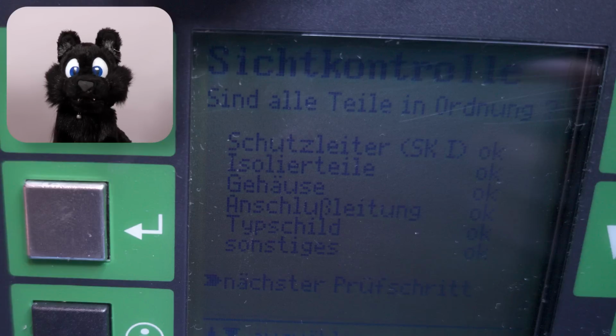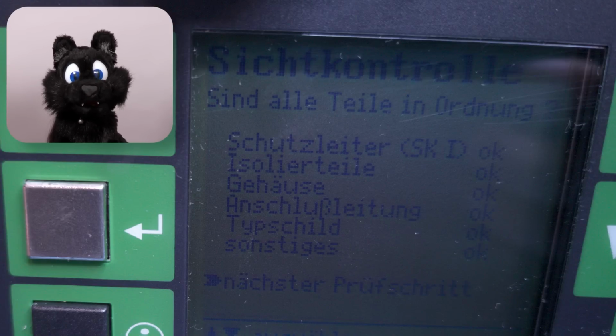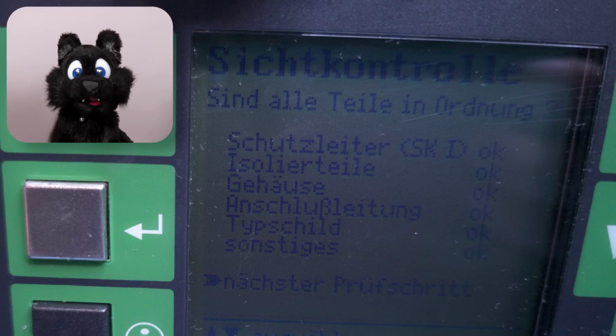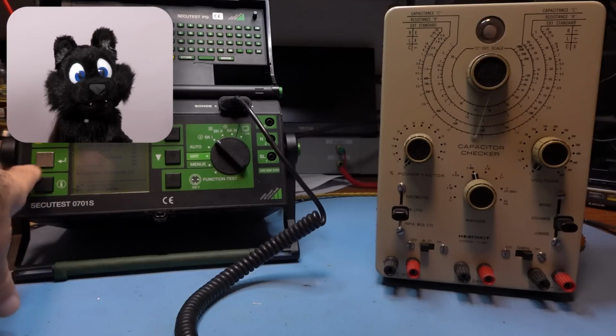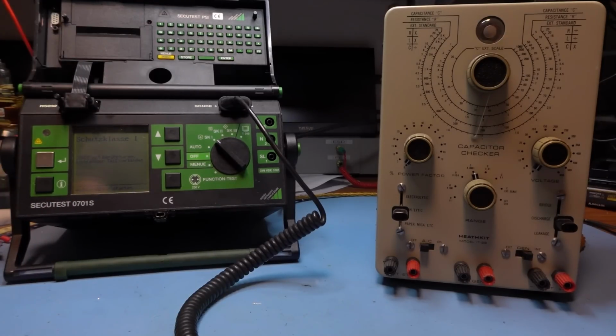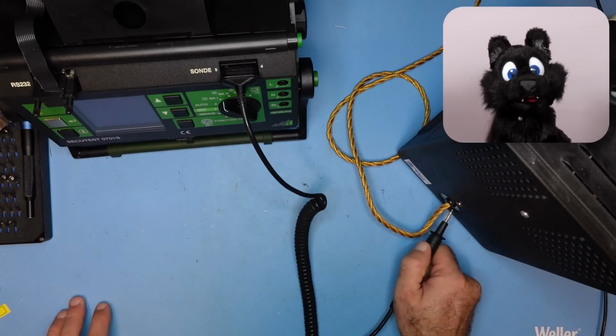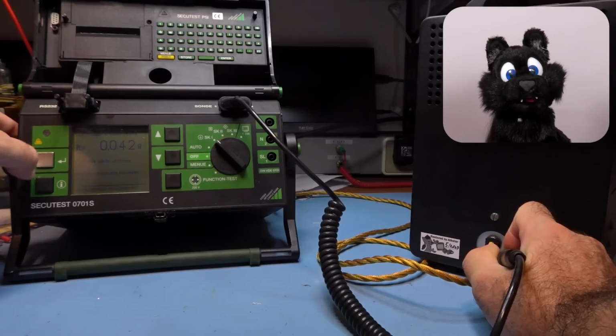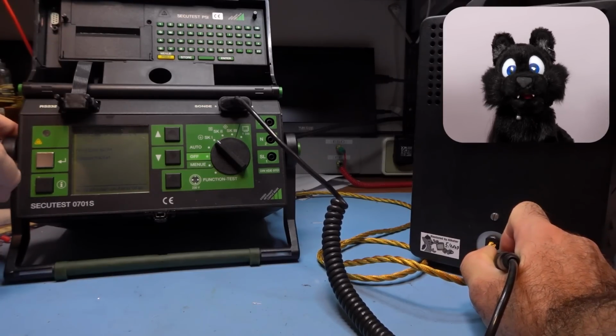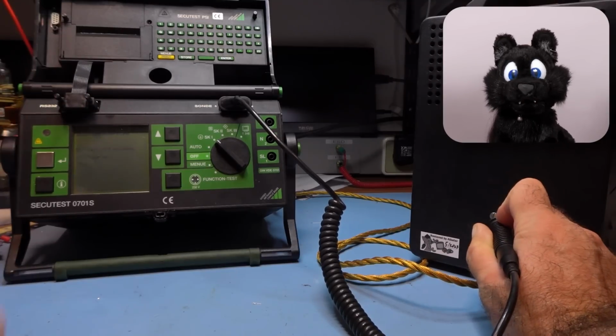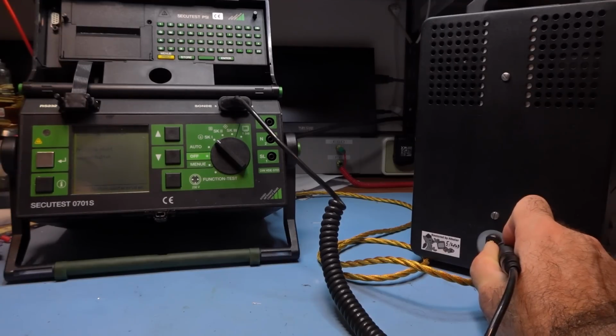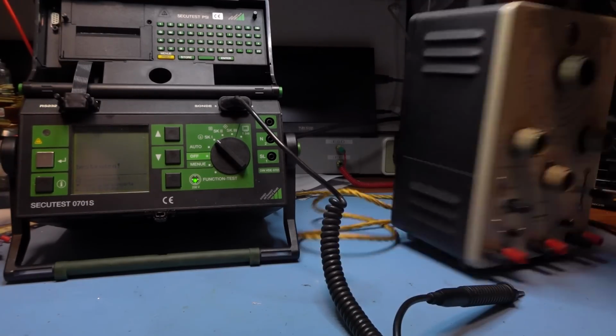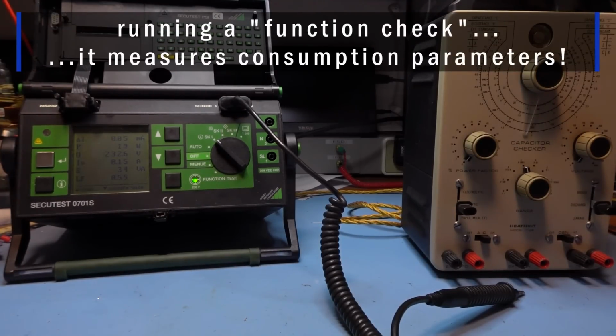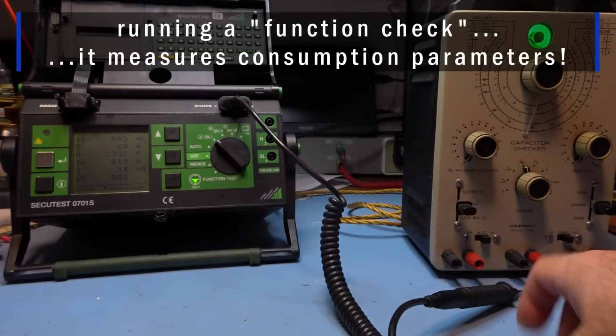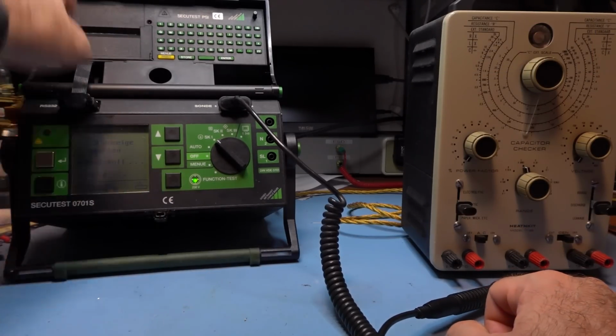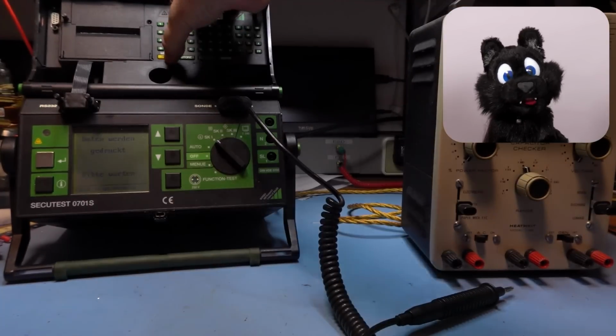First, visual inspection. It is funny to see that you can set all of the items pass or fail when, to the best of my knowledge, the test isn't allowed to continue if any of these fail. Meh. The next key part for the SK1 type device, that is a device with a protective earth connection, one needs to poke all exposed metal parts with the probe to check earthing continuity. And done, printing a report and saving the result.